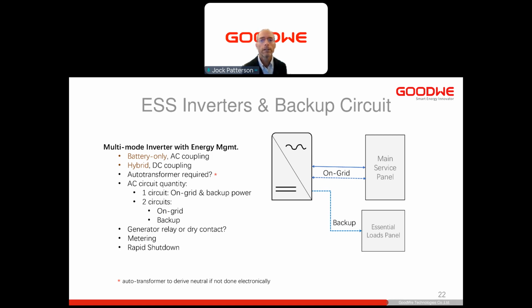These inverters typically come in two designs. Either there's a single AC circuit leaving them, as represented by the solid blue line here to the main panel, or the dotted line represents two circuits, where we have an on-grid circuit that opens up when the grid is lost, and then there's a backup circuit in its place. The two-circuit design is great for essential load panels, and the single circuit is better for full home backup, but you can use either one for both cases generally.